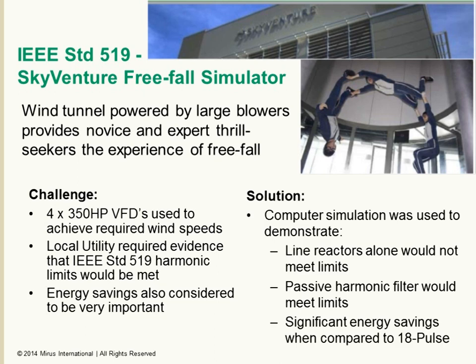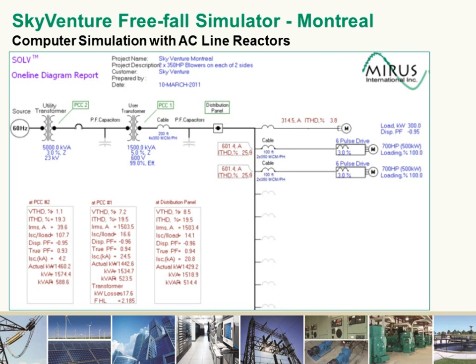The consultant considered various options and used Mirus' free computer simulation software, known as SOLV, to identify the best solution. Both reduction in harmonics and energy savings were considered. First consideration was the use of AC line reactors, since they were the simplest and lowest cost option. So what we show here is two of the variable speed drives combined, two 350 horsepower variable speed drives combined for a 700 horsepower load, and a second set of two 350 horsepower VFDs combined for a 700 horsepower load.